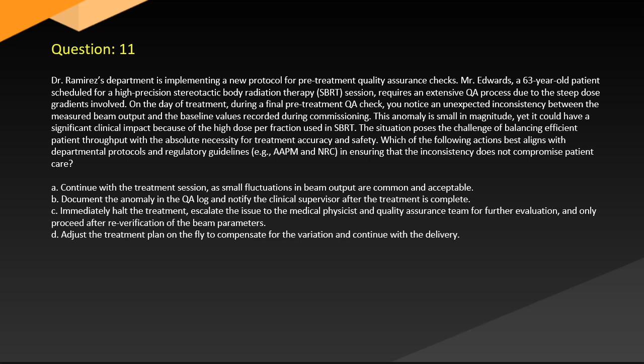A. Continue with the treatment session, as small fluctuations in beam output are common and acceptable. B. Document the anomaly in the QA log and notify the clinical supervisor after the treatment is complete. C. Immediately halt the treatment, escalate the issue to the medical physicist and quality assurance team for further evaluation, and only proceed after re-verification of the beam parameters. D. Adjust the treatment plan on the fly, compensate for the variation and continue with the delivery.